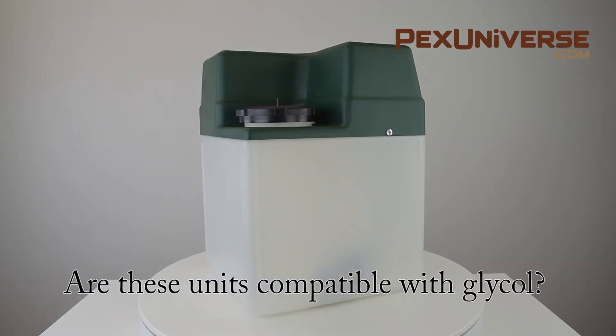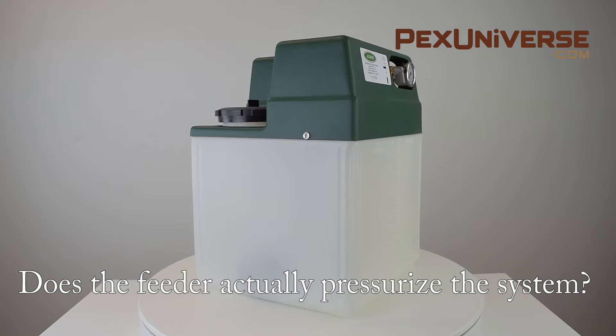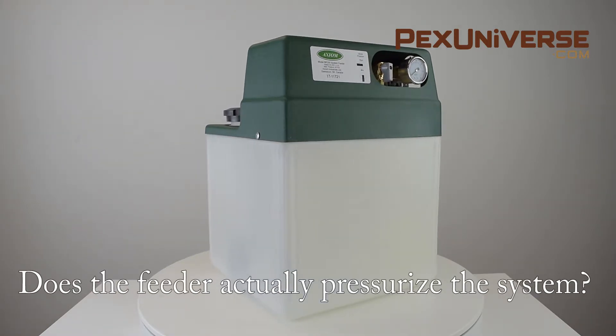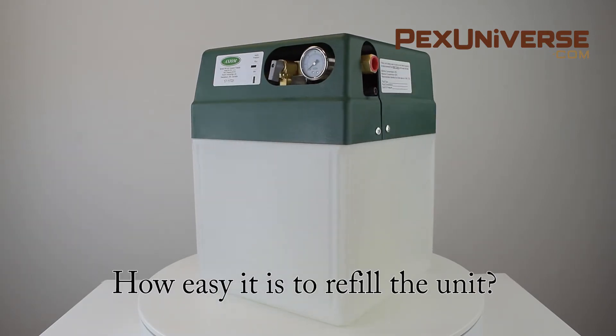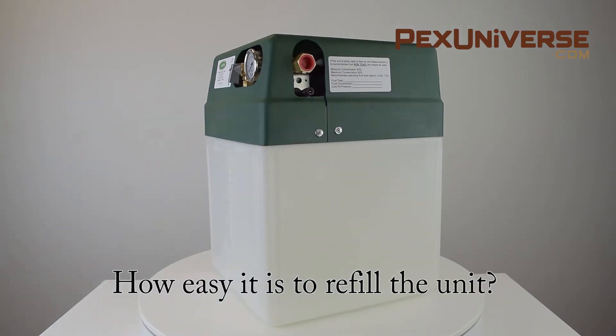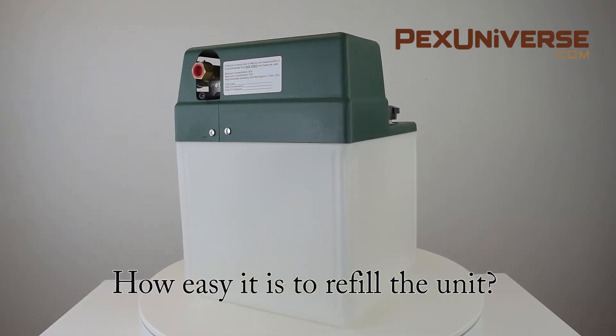These units are compatible with glycol, up to a 50-50 water and glycol mix. A pressure switch will turn the pump on when the system pressure falls below the feeder preset pressure. All feeders have a 5 inch minimum opening which makes it easy to refill the unit and even to mix a solution inside.